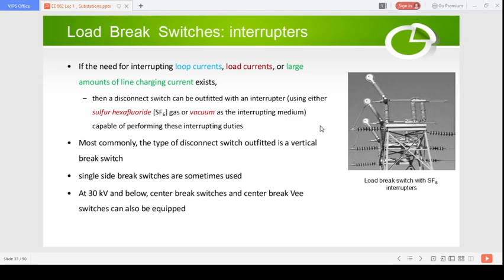Okay, let's talk about the load break switches. Just an isolator with an arcing horn will not act as a load breaking switch. There should be a special arrangement to make the switch a load breaking switch. This type of switch we also call the interrupter. Here you can see the load breaking switch with an SF6 interrupter in this figure.